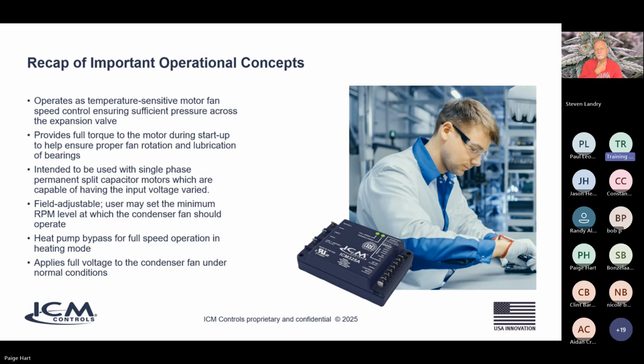So let's recap the important operational concepts of this control. It operates as a temperature sensitive motor fan speed control, ensuring sufficient pressure across the expansion valve. It provides full torque to the motor during startup to help ensure proper fan rotation and lubrication of the bearings. That's your hard start. It's intended to be used with single phase permanent split capacitor motors. Not only intended to be used that way, it has to be used that way. These do not work on electronically commutated motors, EC motors. It will not work with those. It's only for permanent split capacitor motors, which are capable of having their input voltages vary.